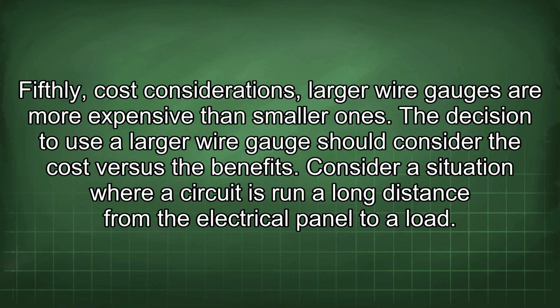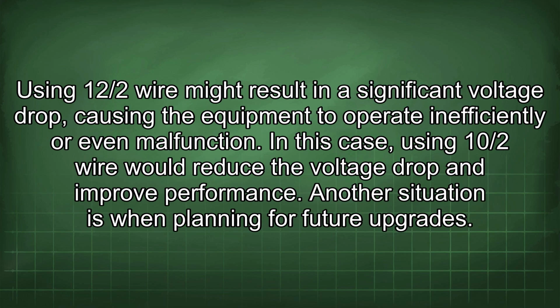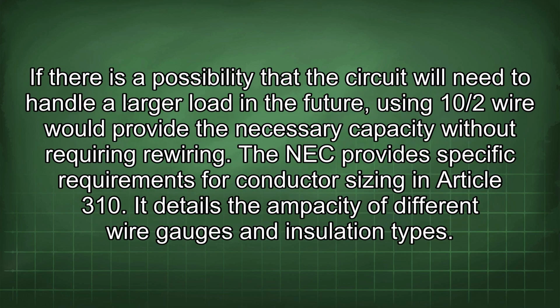Consider a situation where a circuit is run a long distance from the electrical panel to a load. Using 12/2 wire might result in a significant voltage drop, causing the equipment to operate inefficiently or even malfunction. In this case, using 10/2 wire would reduce the voltage drop and improve performance. Another situation is when planning for future upgrades. If there is a possibility that the circuit will need to handle a larger load in the future, using 10/2 wire would provide the necessary capacity without requiring rewiring.